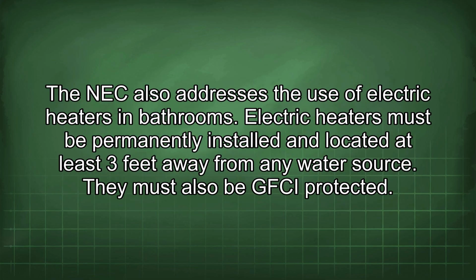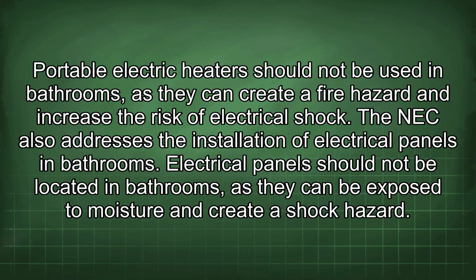The NEC also addresses the use of electric heaters in bathrooms. Electric heaters must be permanently installed and located at least 3 feet away from any water source. They must also be GFCI protected. Portable electric heaters should not be used in bathrooms, as they can create a fire hazard and increase the risk of electrical shock. The NEC also addresses the installation of electrical panels in bathrooms.